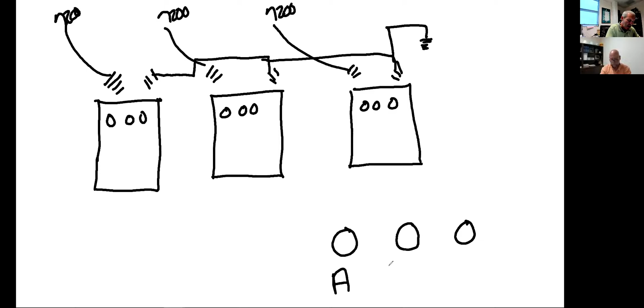All right, in this configuration, I'm going to get 120 off the neutral, which is grounded, and another 120, and combined together I'm going to get 240 volts. That's how they come from the factory. Okay, I need to convert this transformer to be all 120 only. What do I need to do with the leads?